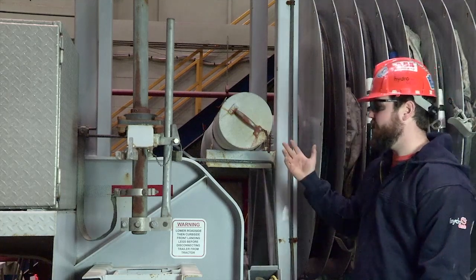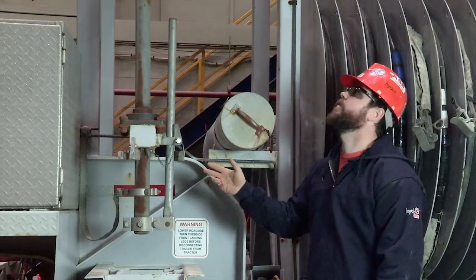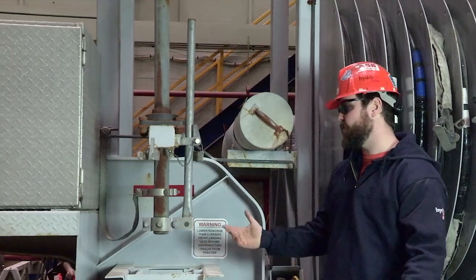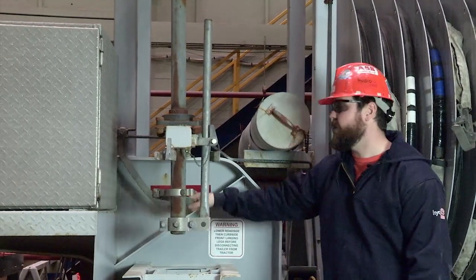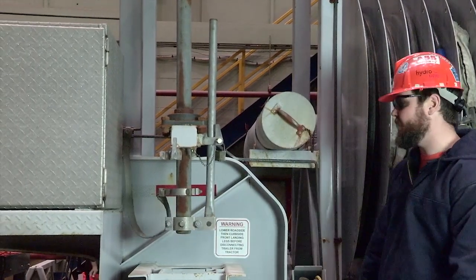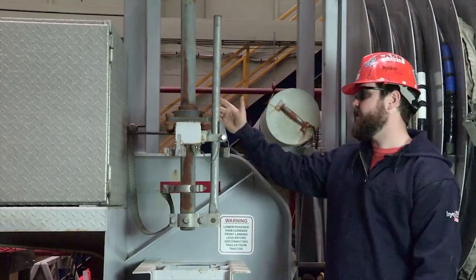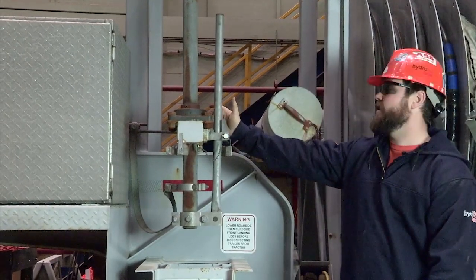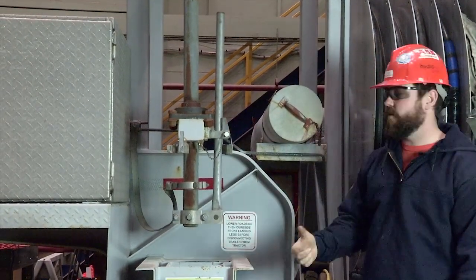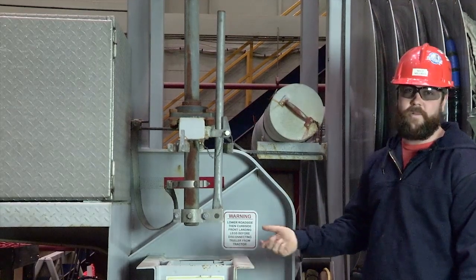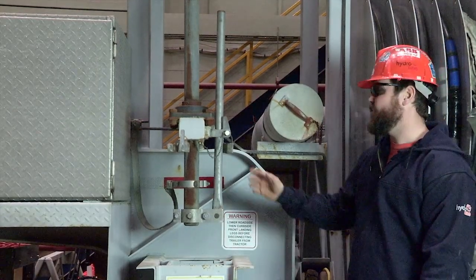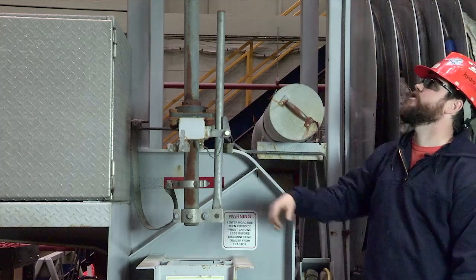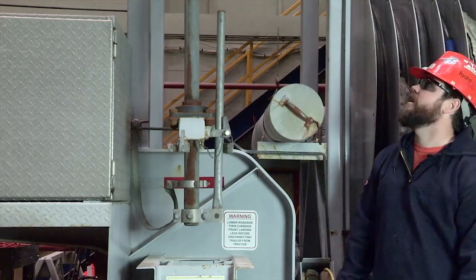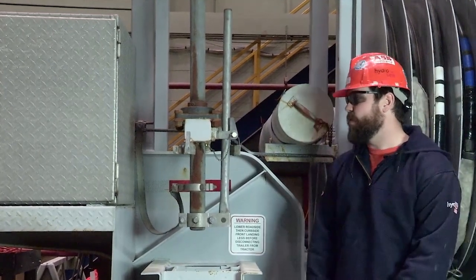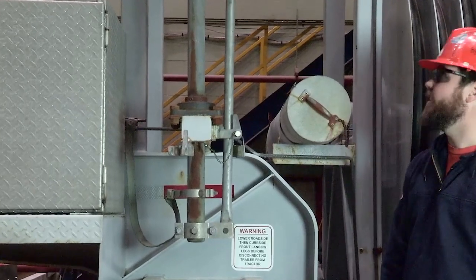And once that's done, we can move on to the switch here. First things first, you've got to make sure that the switch is grounded. There's a good connection, because again, with theft, it could go missing. Any grease nipples or anything like that, you want to go ahead and grease it. Operate the switch first, make sure how it's running, whether it's operating smoothly or how rough it is. Make sure there's nomenclature on the switch. As you can see, this one's just Dymo tape, so it needs to be improved with some decent nomenclature.